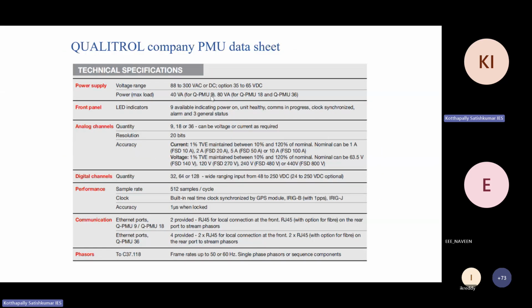So here it's a 9 channel, 18 channel, or 36 channel PMU — you can understand these are multiples of 3. A 9 channel PMU means you can take 3 voltage (RYB) and 3 current (RYB) inputs. In an 18 channel PMU, generally only one bus voltage is taken, and the remaining channels are for currents. So 9 channels means R, Y, B phase of voltage, and the remaining 6 are for two lines, each line having RYB — so it can measure two lines.